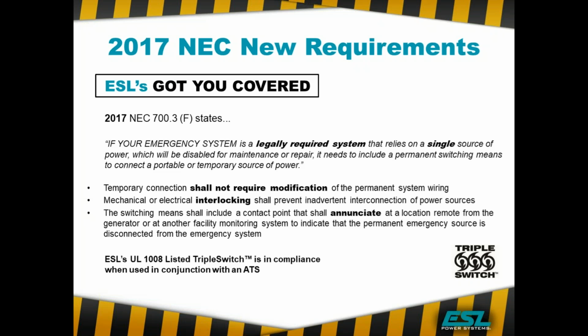What is legally required also is determined by the authority having jurisdiction, or by the state, the county, or the city, or the district that may have codes that say some facility is legally required to have a permanent generator. So that would be something like a shelter in place. We do a lot of gymnasiums at high schools because in certain areas they're designated as shelter in place. They have kitchens and other facilities there. And so they have to have a permanent generator, and that generator has to be backed up.